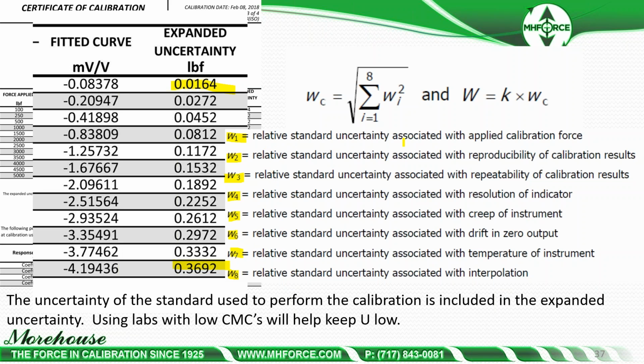It's the relative standard uncertainty associated with applied calibration force. As I said, this one's my favorite for 2 reasons. One, the majority of the time we're using dead weights and we can give very, very low numbers. But the second is it follows that metrological traceability pyramid where the uncertainty of the reference standard must be included. And the standard does it for you. It requires it in the standard instead of outside of the standard, where you can have someone having an expanded uncertainty of 0.05 giving you a measurement uncertainty of less than that when you just use the ASTM lower limit factor only.